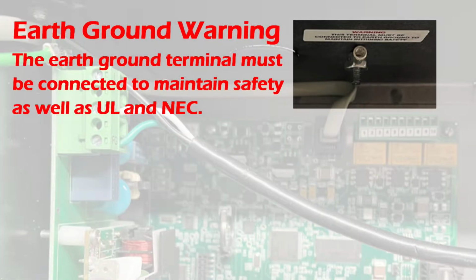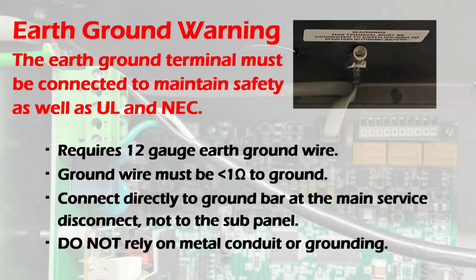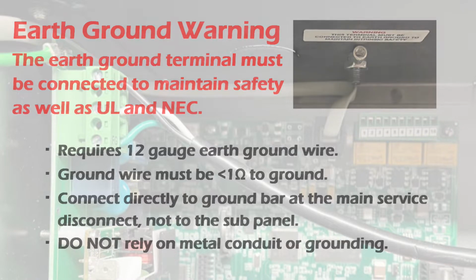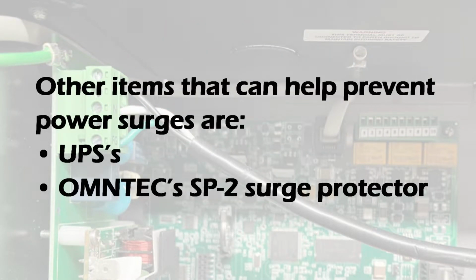An earth ground is also required to be connected as it adds to the intrinsic safety of the controller. It must be a separate ground directly connected to the ground bar at the main service panel. This will also protect the unit from power surges. Other items that can help prevent power surges are UPSs and OMNTEC's SP2 surge protector.